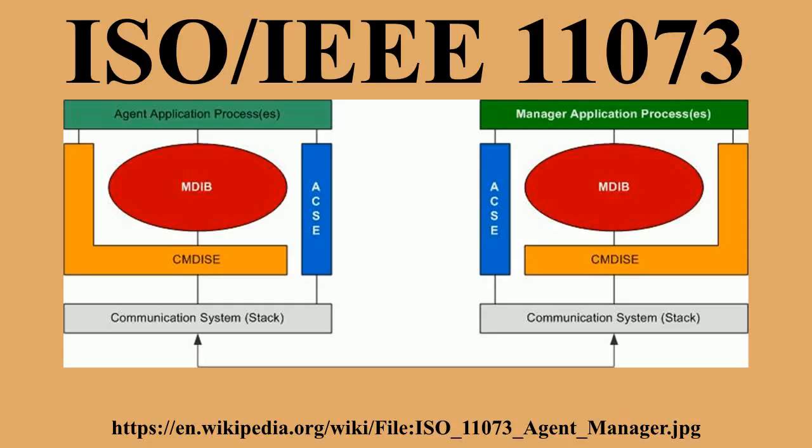Nomenclature. Within this standard, nomenclature codes are defined. These give the possibility to clearly identify objects and attributes in relation to the so-called OID code. The nomenclature is divided in partitions to demarcate codes with regards to content and functions. Programmatically, these codes are defined as constants. Those can be used by a pseudonym. Example in C++: #define for the partition object infrastructure, #define the object simple medical device system.